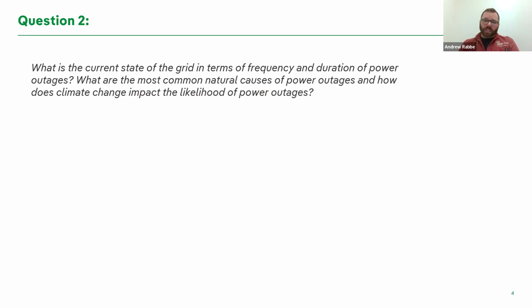If they start getting voltage issues, that's usually when they'll upsize the transformer or split the load. Or if your lights start to dim, they could call out a troubleshooter - they work 24/7 around the clock - and they'll come out, put what's called an amp probe, wrap it around the line and see if we're getting towards the high end of that transformer. In which case they put in a work order to change out the transformer to get everything running again. There's no specific set number on how many customers are fed from each transformer - it's more or less case-by-case.